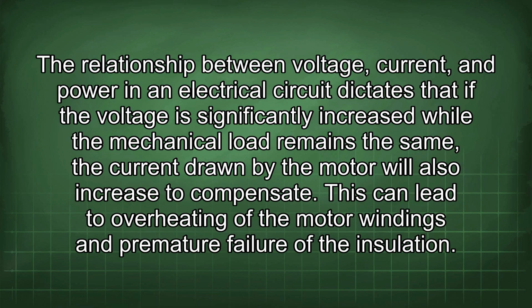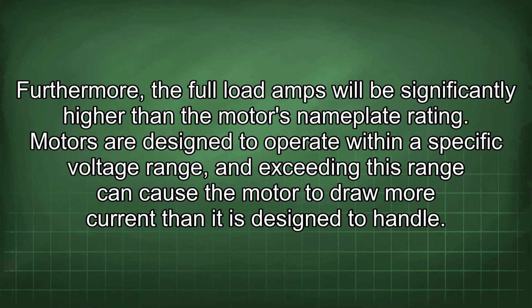The relationship between voltage, current, and power in an electrical circuit dictates that if the voltage is significantly increased while the mechanical load remains the same, the current drawn by the motor will also increase to compensate. This can lead to overheating of the motor windings and premature failure of the insulation. Furthermore, the full load amps will be significantly higher than the motor's nameplate rating.